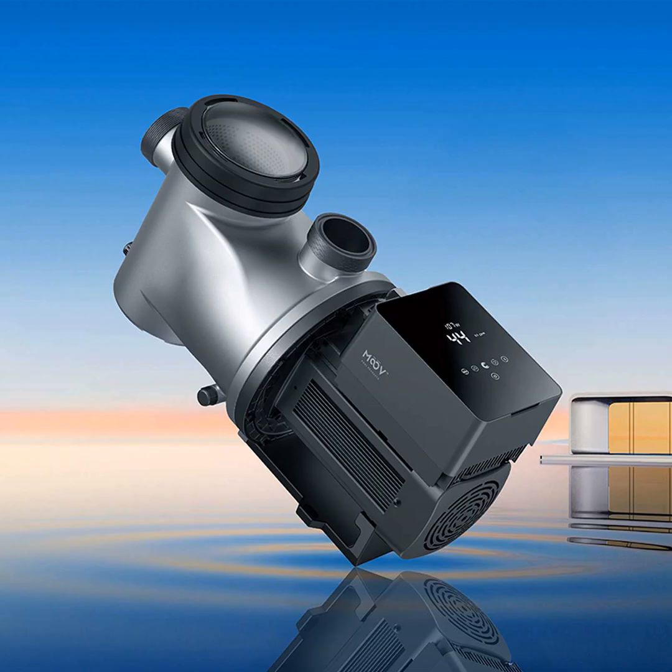So the initial launch, when the product does start, does the warm up, does the self priming, then does multiple set speeds, then has a set algorithm saying, okay, these are my 3 reference points. And if the pressure goes above or below the 3 reference points, then I'm going to simply adjust my speed. And that's going to be based on the pressure probe as well as the watts that it is consuming, to have the same efficiency on the product.